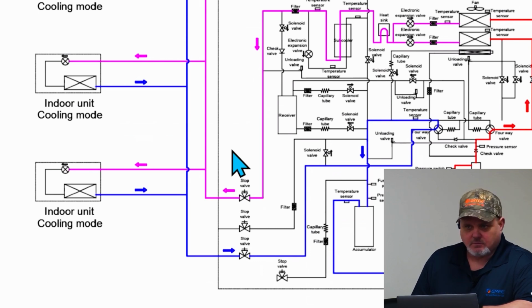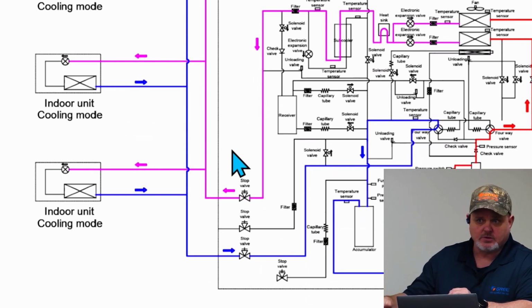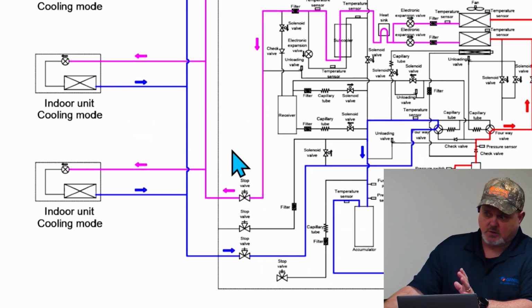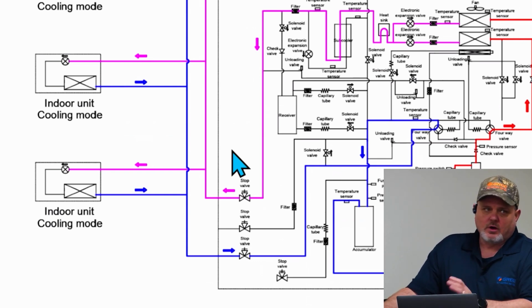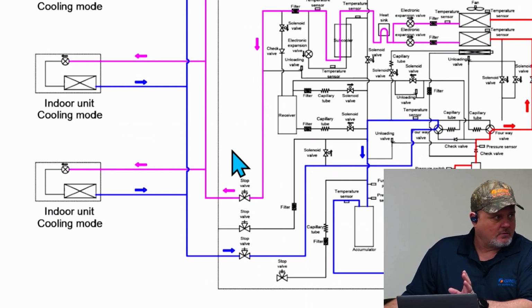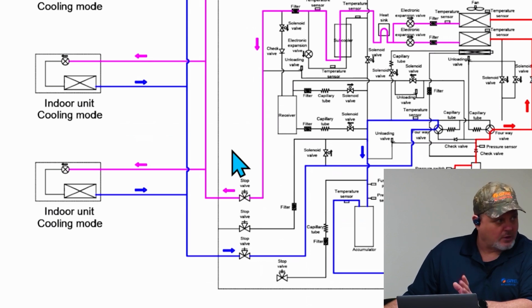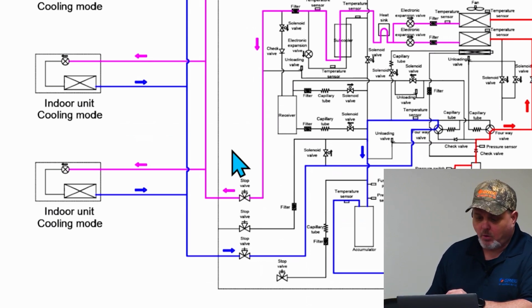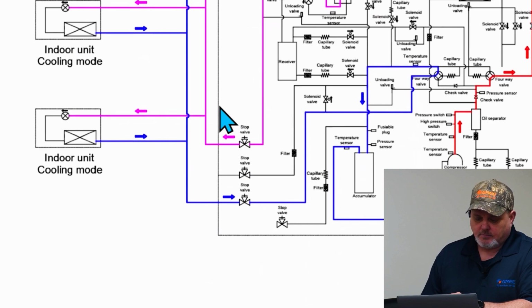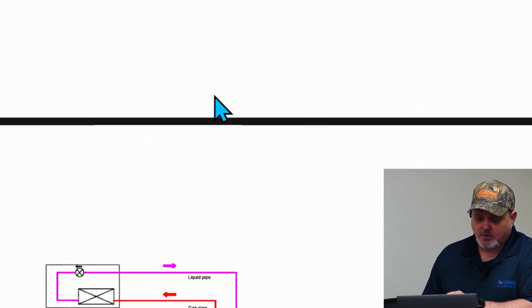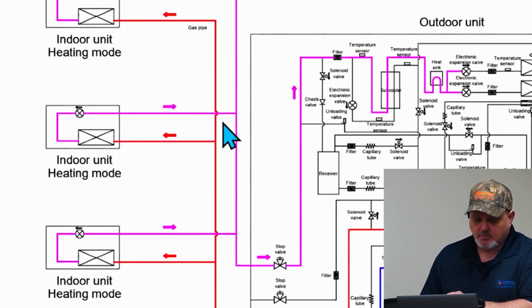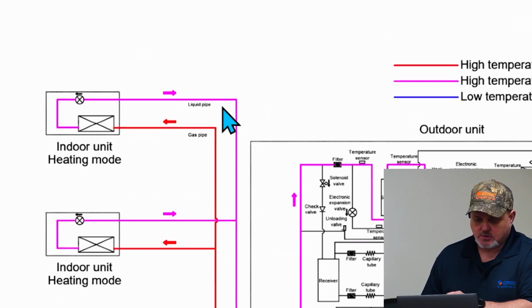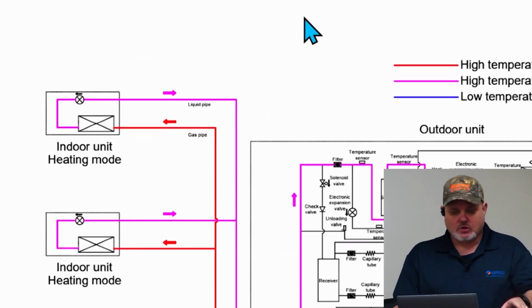And it doesn't matter for heat recovery because you're doing all 3, other than you still need to make sure you're piping them correctly to the mode box. You know, liquid's liquid, high pressure gas, low pressure gas is low pressure gas. But when you're running all 3 pipes, it's a little easier than when you're only going to use 2 of the 3. Yep. So it's very important. And like I said, I'm going to work with the factory to try to get these labeled a little bit better for you guys so you understand it. Okay? So anyway.